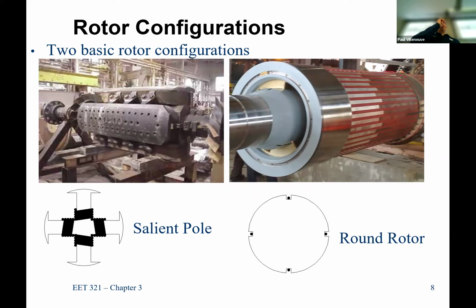If you buy or build a synchronous or induction machine, you have two rotor types. One is a salient pole, basically laminations with slots available. The other is a round rotor, a big hunk of solid metal milled out where you want the windings to go. The salient pole design uses laminations and normally runs at slower speeds than round rotors.